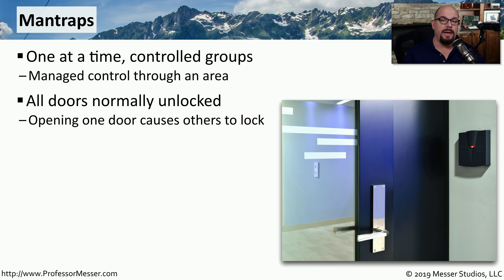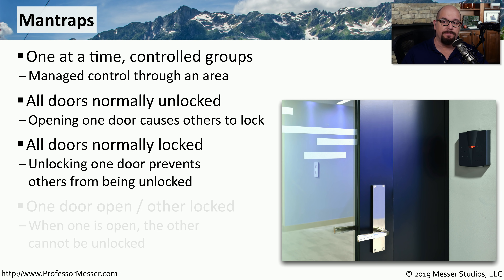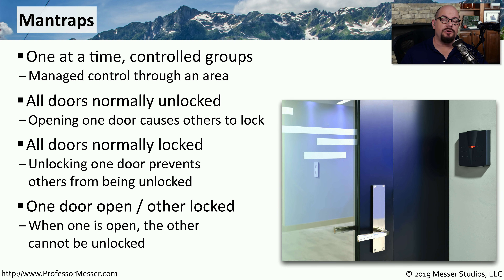One common configuration with man traps is that both doors are unlocked, and as soon as the first door is open, the other door locks, so you can only have one door open at any particular time. Or maybe all doors are locked, and as soon as one person badges in and unlocks that door, all other doors are prevented from unlocking until that door closes behind that person. The real key with a man trap is you never have both doors open at the same time — there's always going to be a controlled flow.